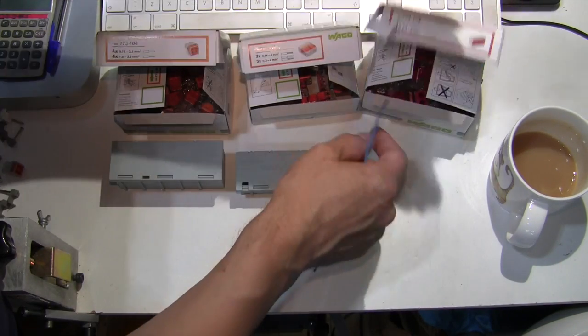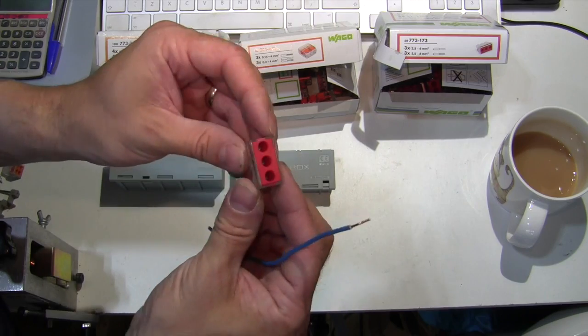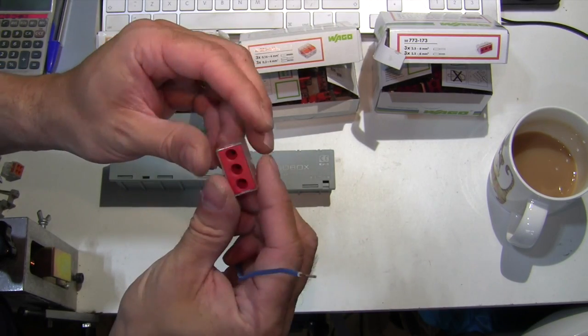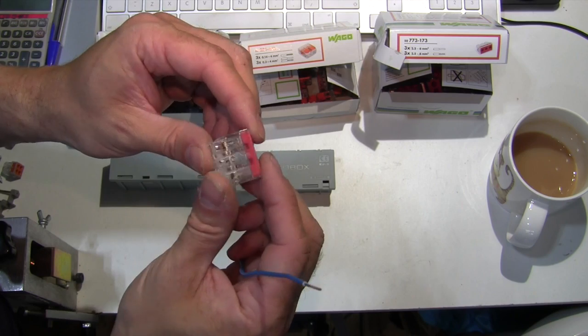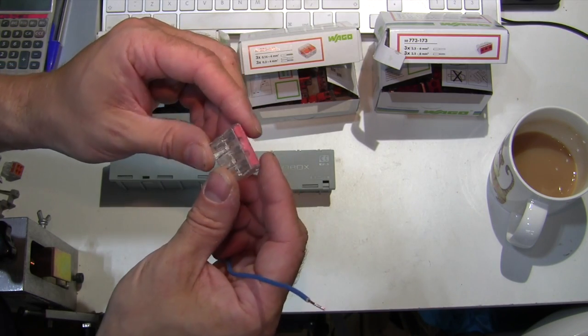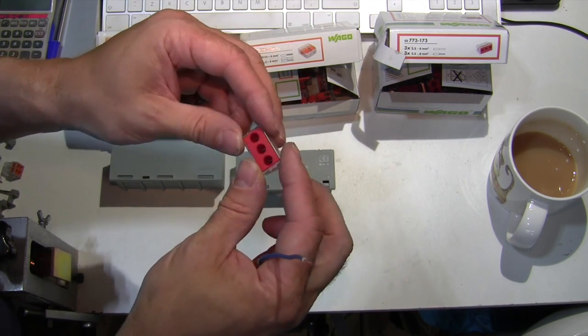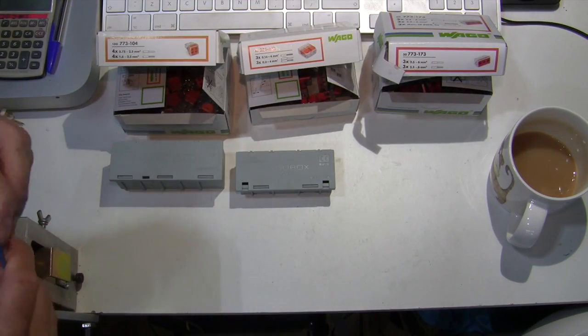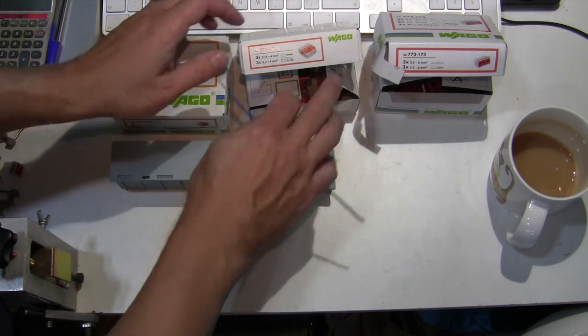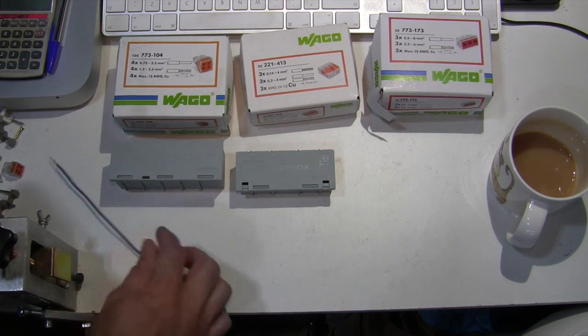And they do various sizes. This one will take a 6mm cable, again three-way, good for those circuits like a cooker circuit where you've got a bit of a thicker cable to cope with and you just need to extend it or whatever. The only thing they don't do, which I wish they did, is like a Y splitter cable. So if you're installing a socket spur onto a piece of ring circuit, you cut the two and a half ring circuit, it'd be nice if they had some kind of wire connector so you could re-splice that and then still take your spur off it. Missing a bit of a gap in the market there, I think.